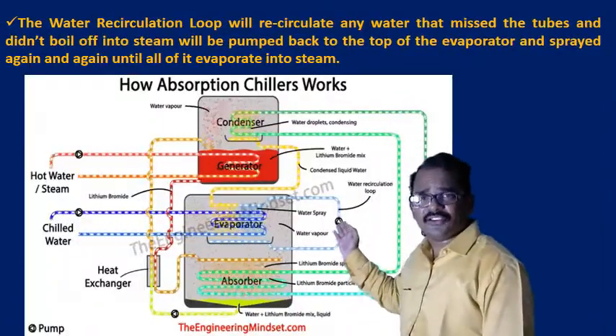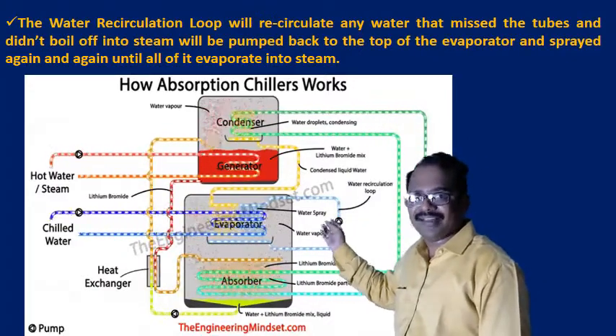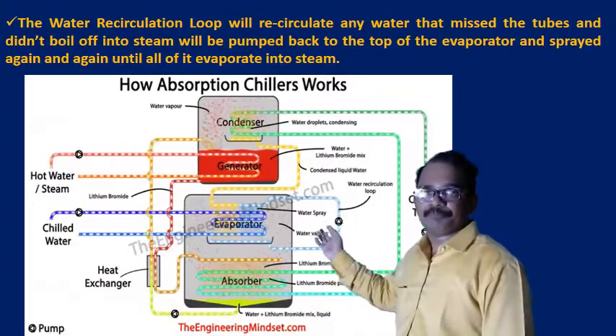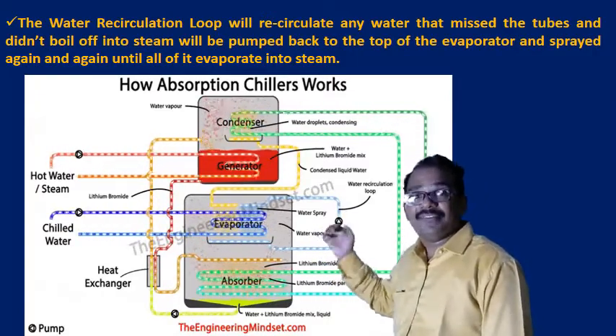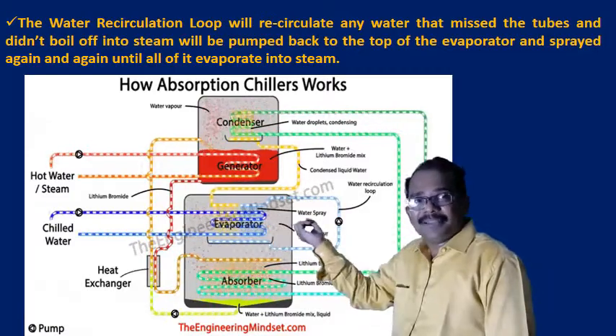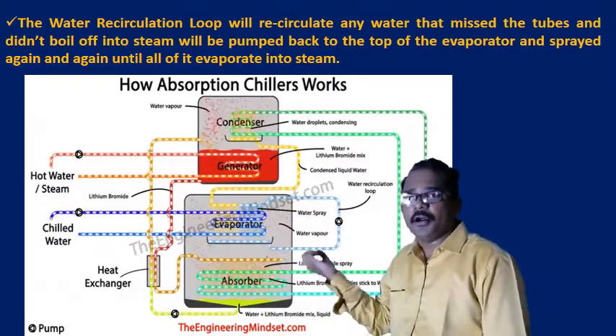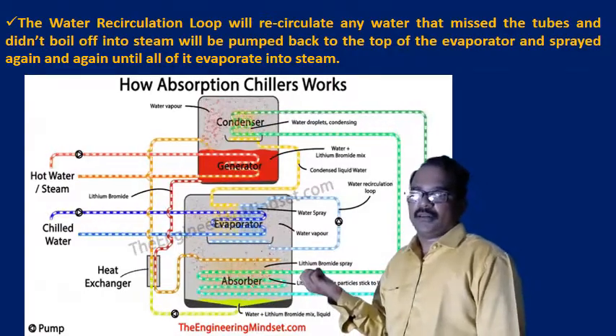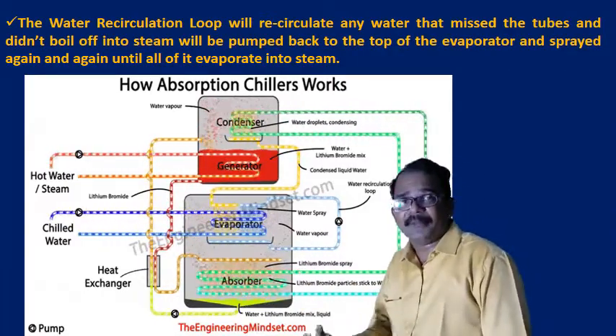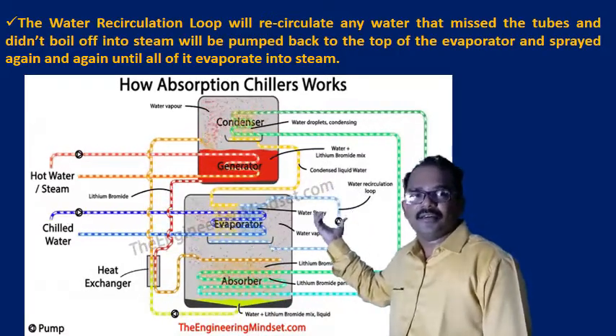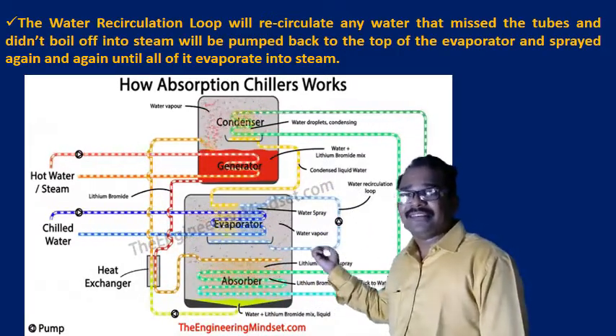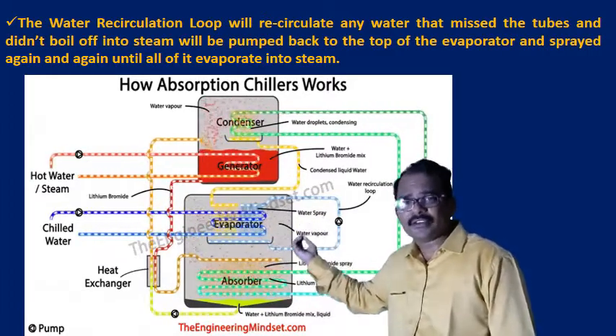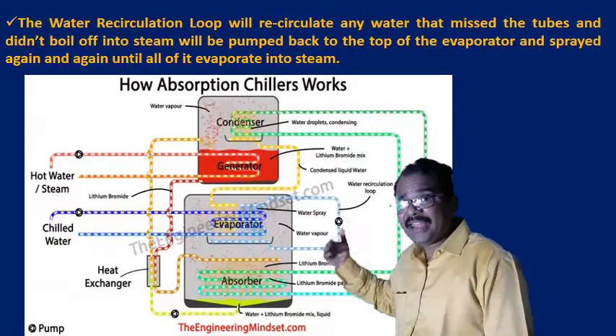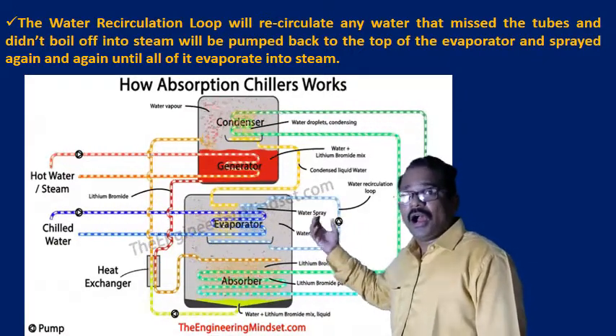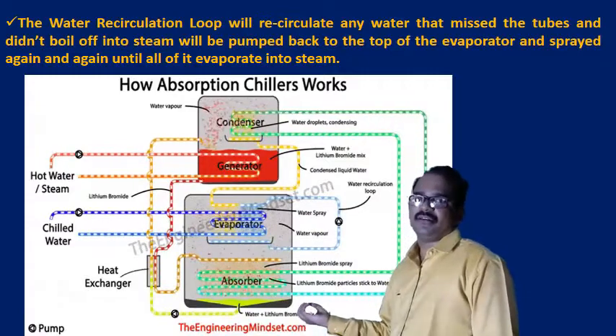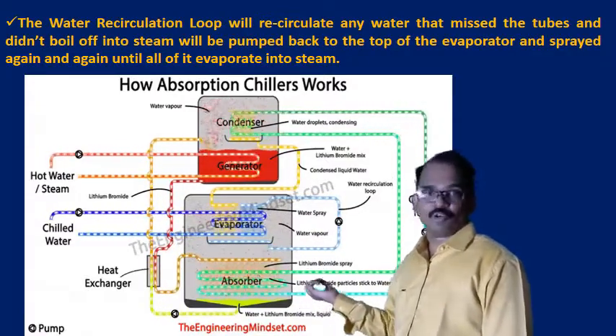Then the water recirculation loop is one more loop which is there in the evaporator section itself. This water recirculation loop will recirculate any water that missed the chilled water tubes and didn't boil off into steam. That amount of water will be pumped back to the top of the evaporator by means of a recirculation pump, and it is sprayed again and again until all of it evaporates into steam. You understand this one, right?